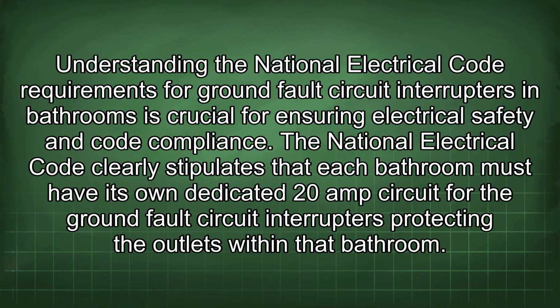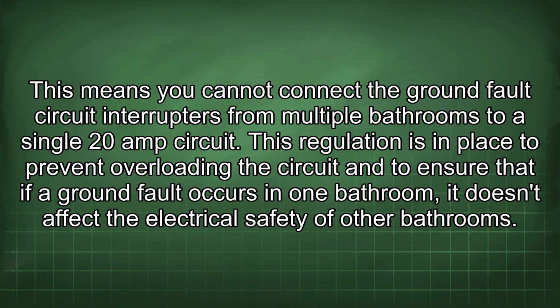Understanding the National Electrical Code requirements for ground fault circuit interrupters in bathrooms is crucial for ensuring electrical safety and code compliance. The National Electrical Code clearly stipulates that each bathroom must have its own dedicated 20 amp circuit for the ground fault circuit interrupters protecting the outlets within that bathroom. This means you cannot connect the ground fault circuit interrupters from multiple bathrooms to a single 20 amp circuit. This regulation is in place to prevent overloading the circuit and to ensure that if a ground fault occurs in one bathroom, it doesn't affect the electrical safety of other bathrooms.